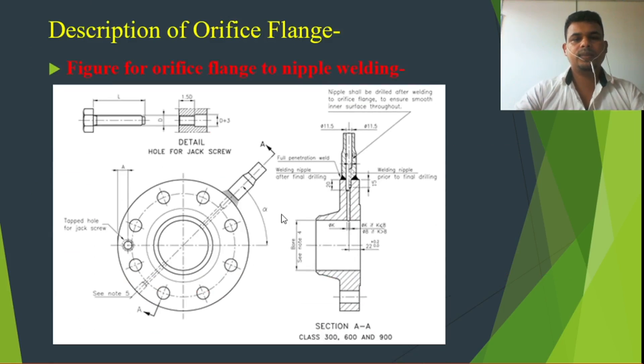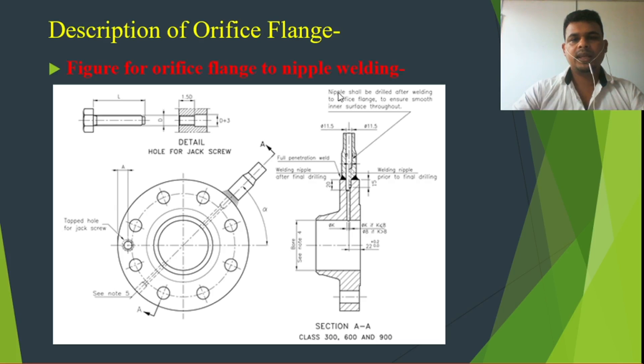Regarding the nipple welding for orifice flanges: in an orifice flange we have two tap holes. From these two tap holes we usually use one side — here we weld a nipple to connect the tubing and to connect to the orifice meter. On the other side we normally put a hexagonal plug or threaded screw to seal it. The welding here requires full penetration welding.